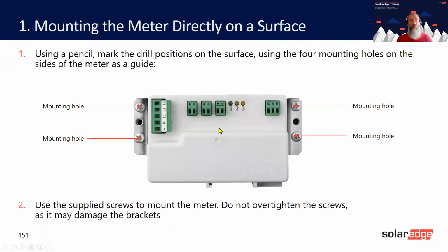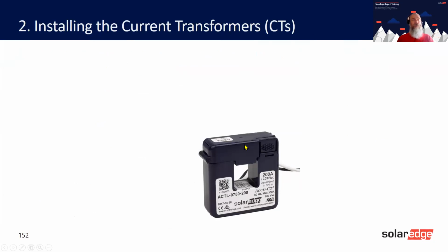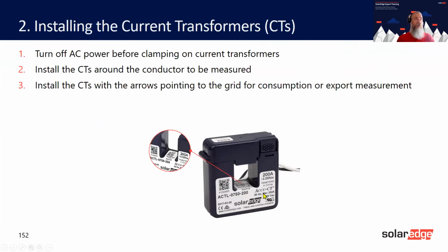All right, okay. So 151, yes, did that one. 152. So this is a CT. On it, you can see, there we go, it's popped up now. On it, you can see we've got here 0.333 volts AC. It's very important that you understand that SolarEdge meters only work on 0.333 volts. We don't do ratio, we don't work on any other voltage, it's only this. You can buy CTs. There's lots of CTs available for this voltage. And should you wish to have larger cables with CTs around them, you can use a Rogowski coil. And again, you can get those at 0.333 volts as well.